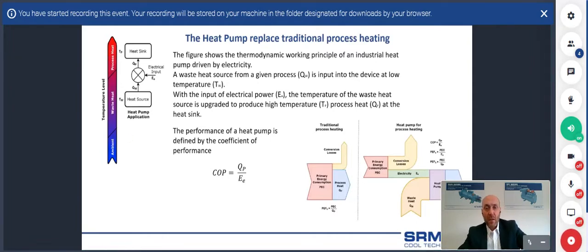that can be used for the process heat. On this page, we can also see another graph that illustrates the comparison between the normal process for the production of heat, which takes primary energy and converts it into process heat. Of course, we have some conversion loss to be considered. And on the right, we can see the system with the heat pump application. Of course, we have the consumption of primary energy sources to produce the electricity. We still have some losses here. But what is different is that the heat pump, located at this level of the process, takes a significant part of the waste heat and converts it to process heat.